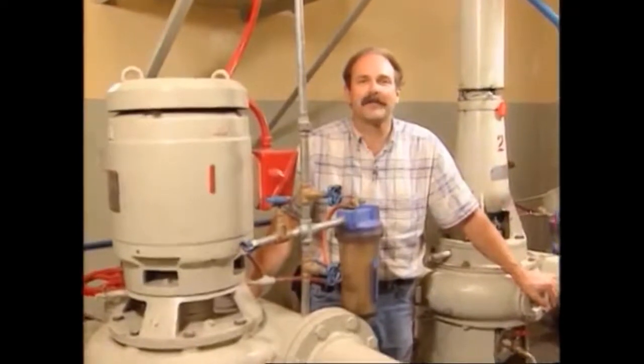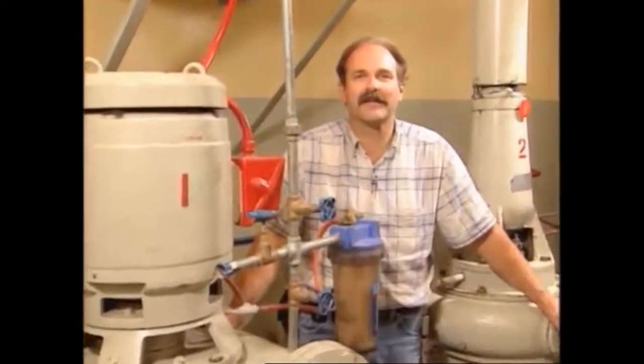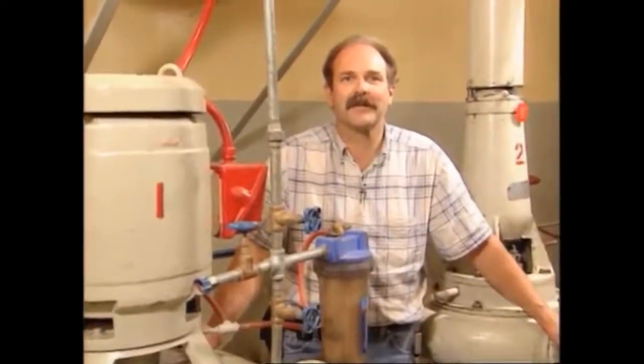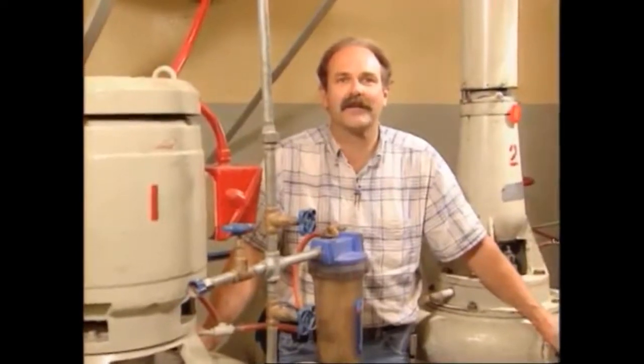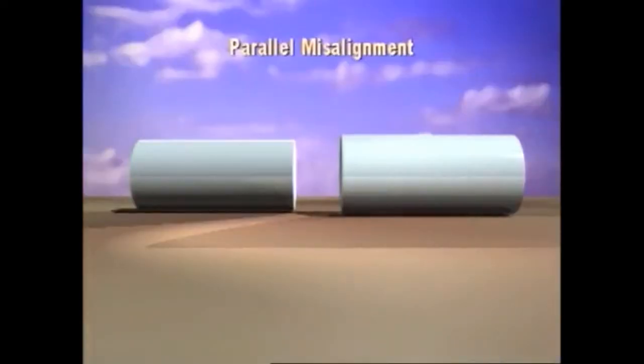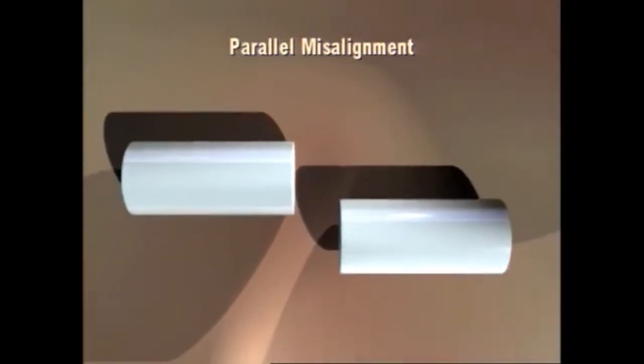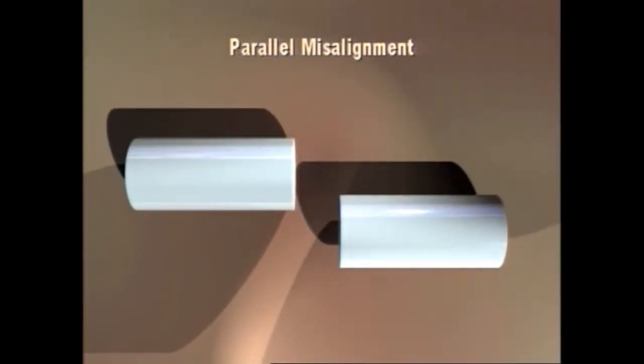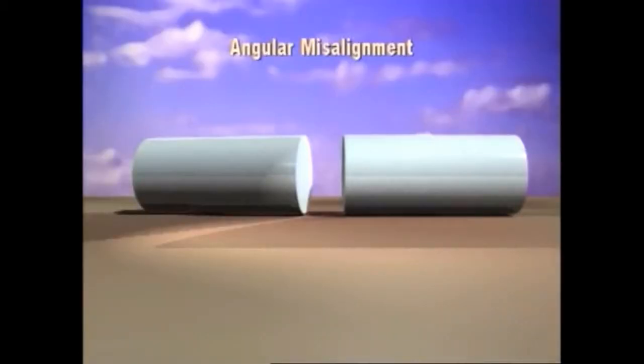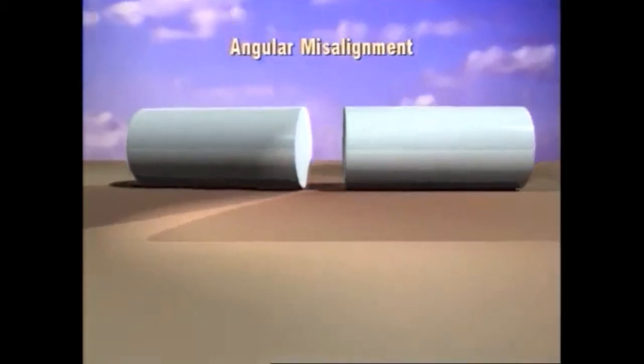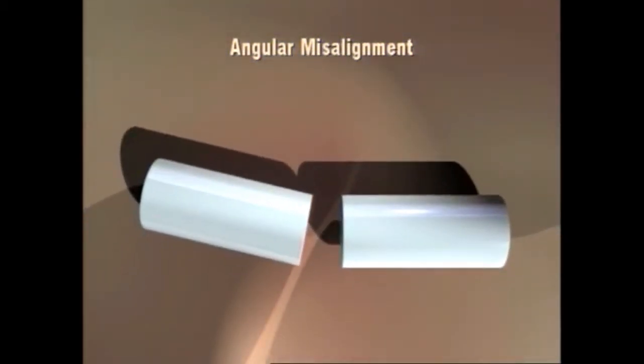When aligning a pump to a motor, there are two basic forms of misalignment: parallel and angular. Parallel misalignment occurs when the center lines of the pump shaft and the motor shaft are offset. The pump and the motor shafts remain parallel to each other but are offset by some amount. The second type of alignment problem is angular misalignment.